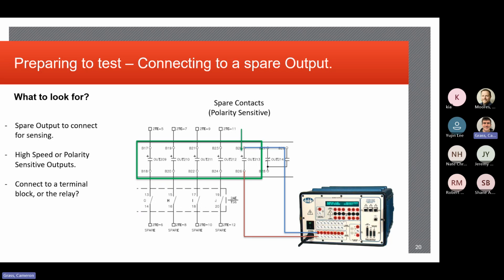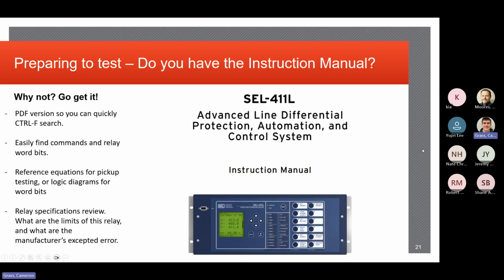As it mentions over here, connecting to a terminal block or the relay, I personally would prefer connecting straight to the relay. That way you don't have any outside contingencies that could apply. Again, you're going off the design intent. Let's say it's connected to a terminal block. That doesn't necessarily mean that the terminal block doesn't go anywhere else. You may be wiring to that, reconfiguring the output to basically close in when you're doing your testing. It could for some reason be connected to some other correlating device in another panel or somewhere else around the control house, which could lead to issues. So it's better safe than sorry to always connect to a spare unwired output in this case. And it may be polarity sensitive too, depending on the situation. So it's always stuff to watch out for.